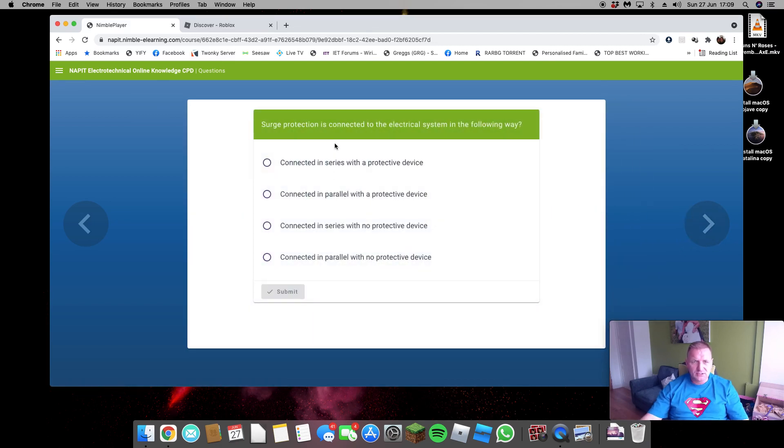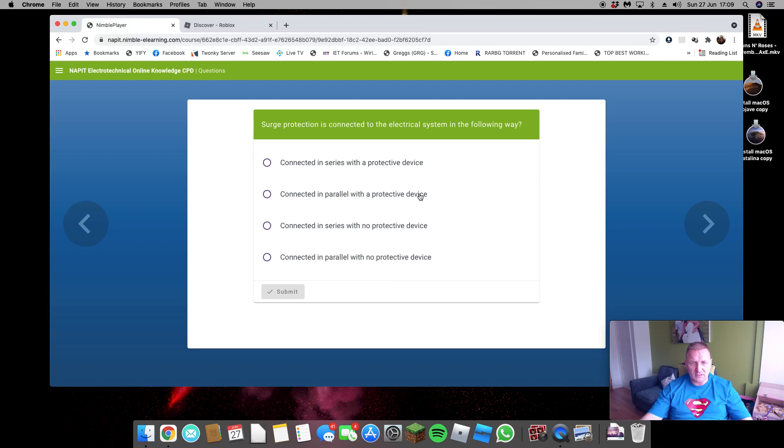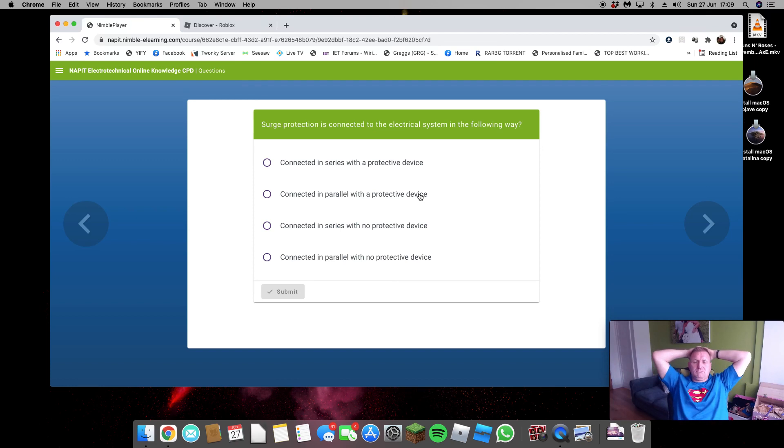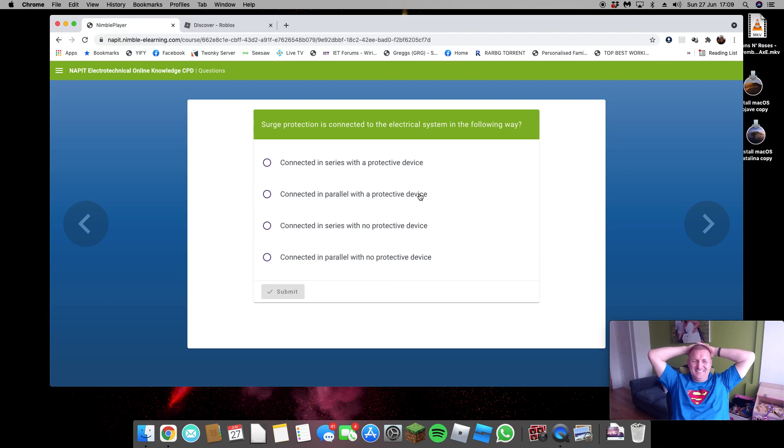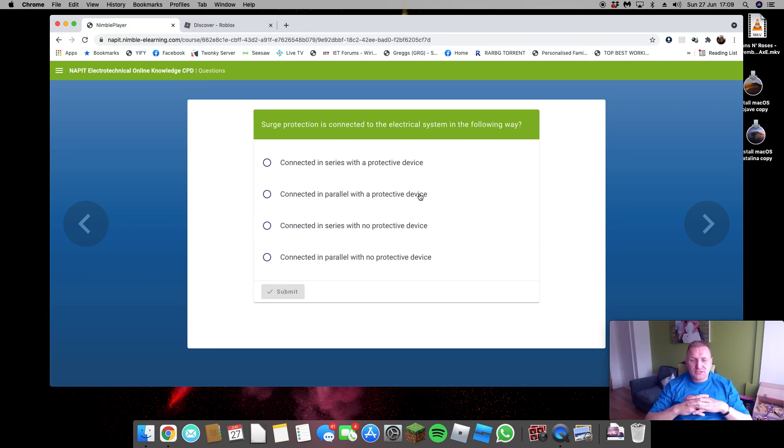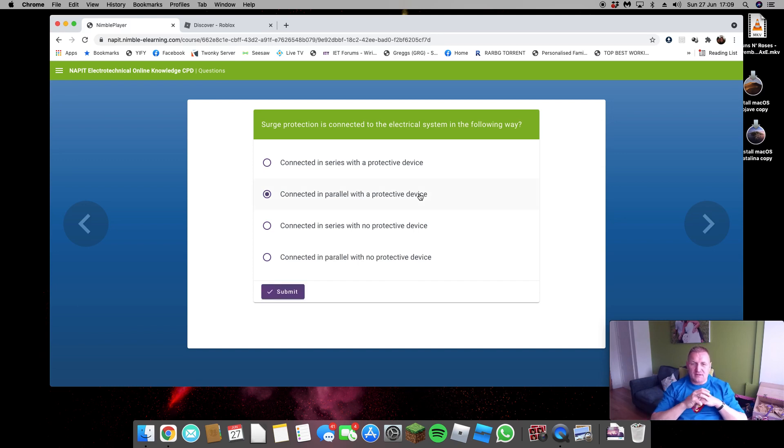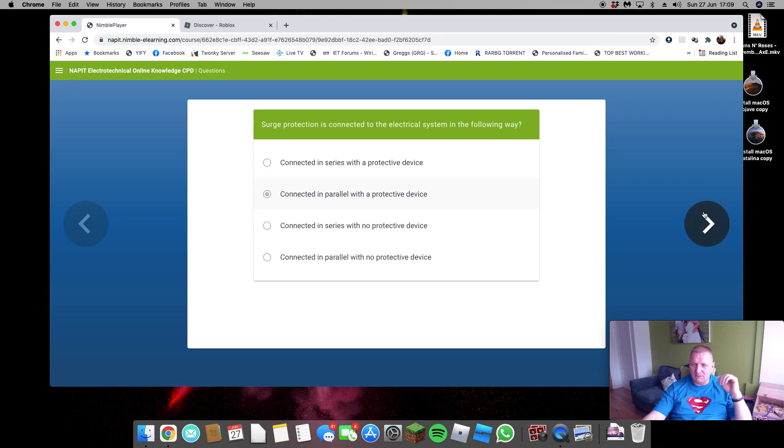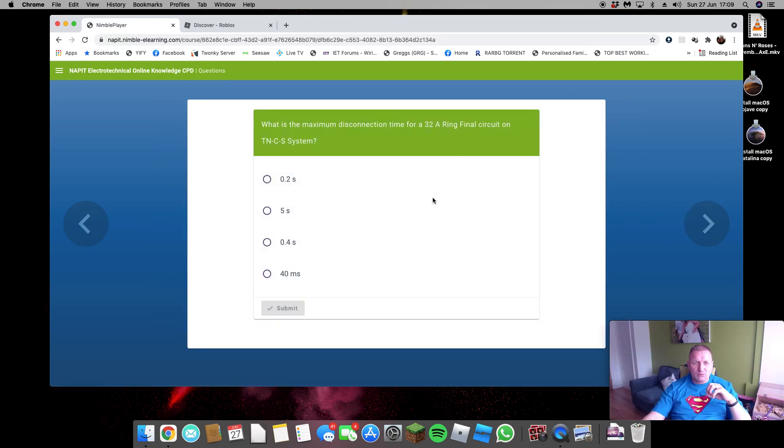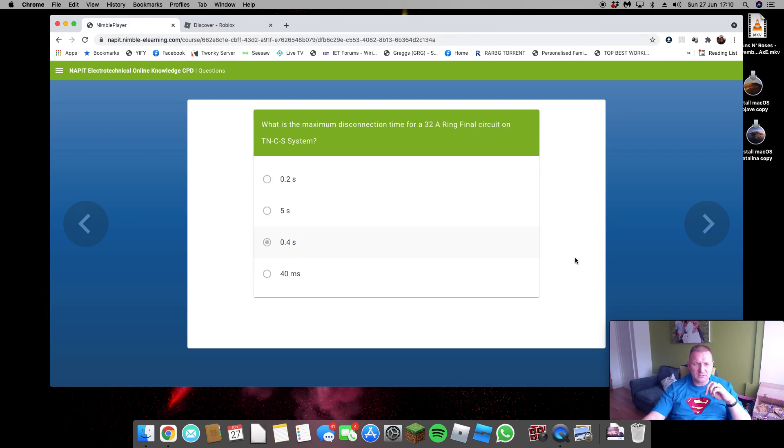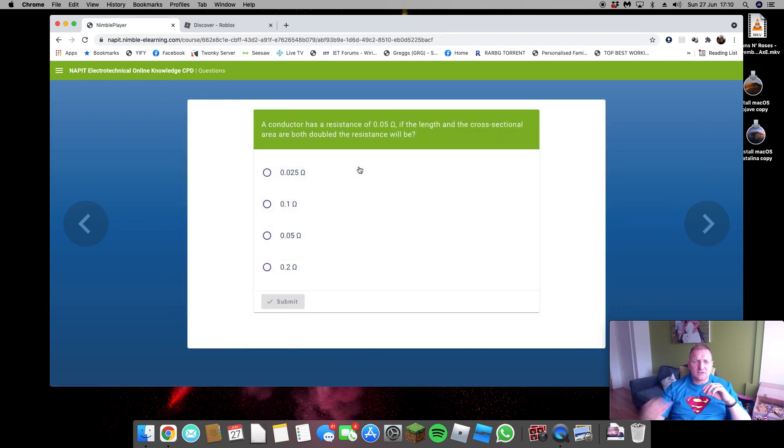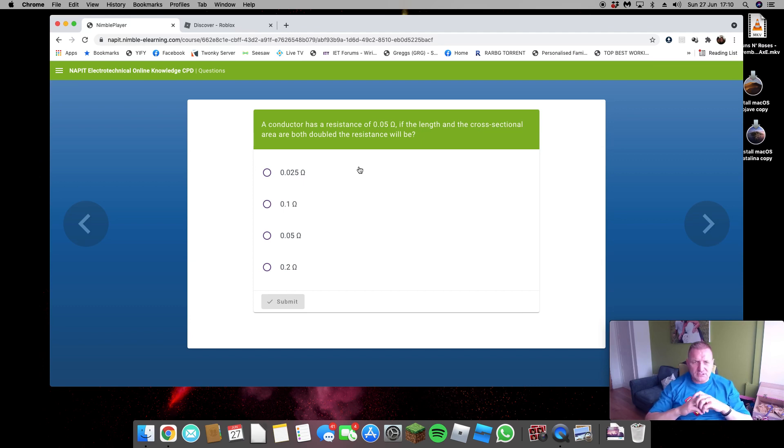Surge protection is connected to the system so it's in parallel with a protective device or with no protective device. Oh, now there are two types of surge protection. This is one of them questions where you've got thrown. They do two types. With a protective device, I'm going to say that cutout fuse is a protective device, but then we're in series with it. Oh, we're not, we're in parallel. So we'll go without. Let's bugger it, let's run with it. I'm not going to argue all day. What's the maximum disconnection time for a 32 amp ring final circuit on a TN-C-S? 0.4 seconds. Conductor has a resistance of 0.05 of an ohm if the length and the cross-section are actually both doubled. It's the same. That's the right answer.